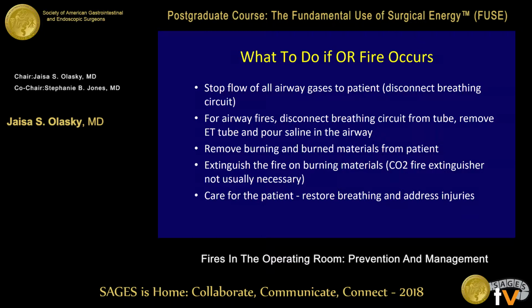First, you want to stop the flow of airway gases to the patient, which is often disconnecting the breathing circuit. Now, if this is an airway fire, like a tracheostomy case, for example, you not only have to disconnect the breathing circuit, but you actually have to extubate the patient, and it's suggested that you would then pour saline into the airway. One strategy that people use is to keep a syringe of saline available for these airway cases, so in the event of a small spark, they can immediately apply that right away before they even get to the point of having an actual fire.